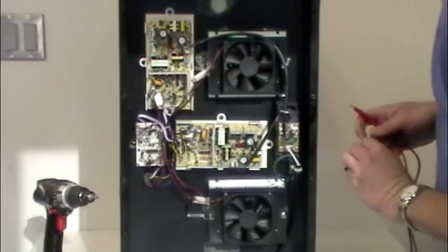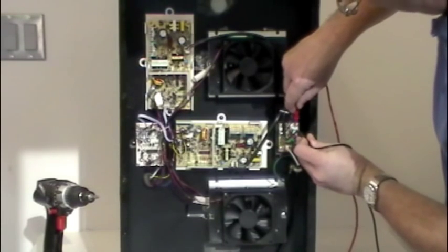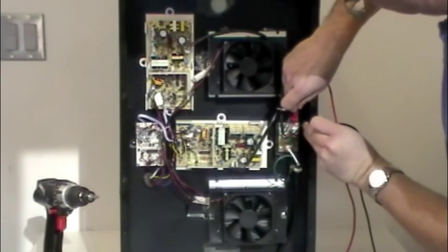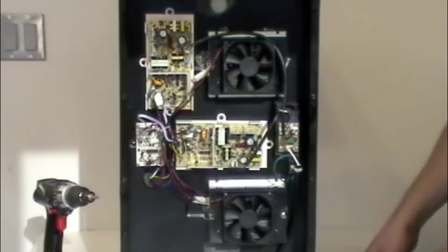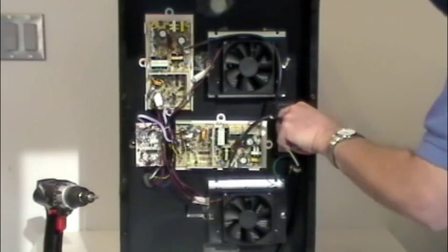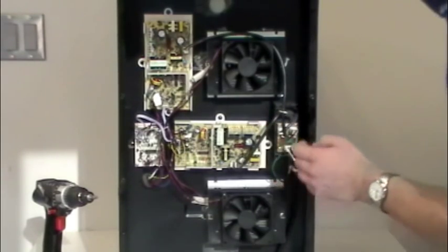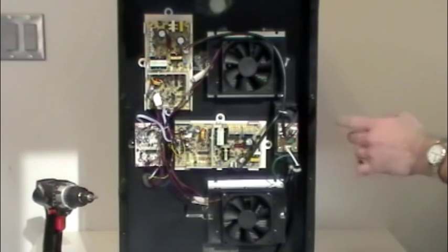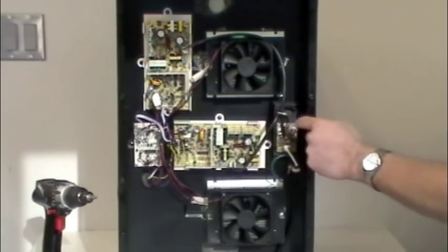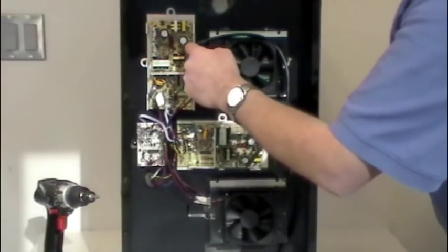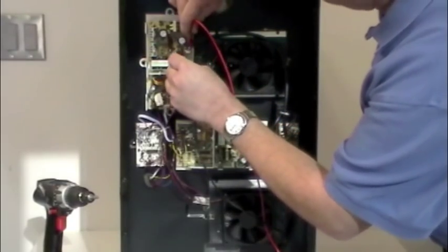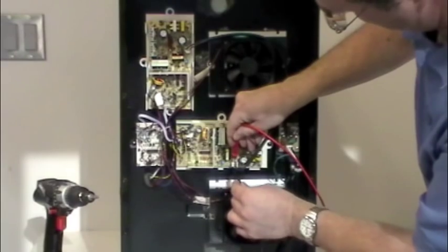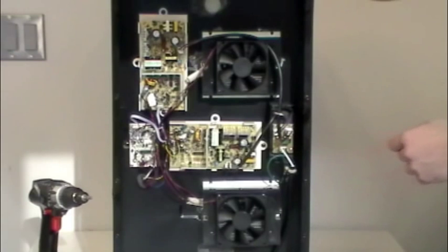We're going to set our meter to AC volts. This one here, we could probably do 200 or 750. Your meter is going to be different, but you should know how your meter works already. So we're going to set this for AC voltage. We would plug the unit in. And we're going to back probe this connector. And that will tell us, this one coming in here with this ground lead, that will tell us whether we have power coming in. Once we've determined whether we do or we don't, and in this case we'll assume that we do, we're going to come up here and we're going to back probe these. You can do these by just back probing these connectors or you can come up here and back probe off this side of the connector. If we've got power coming in but we've got nothing coming out, then we need to replace that board. You'll need to call customer service and we'll get the board ordered.